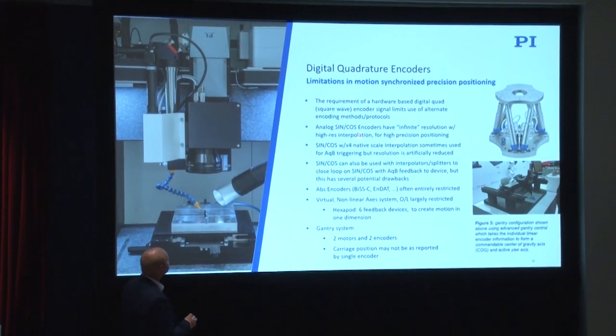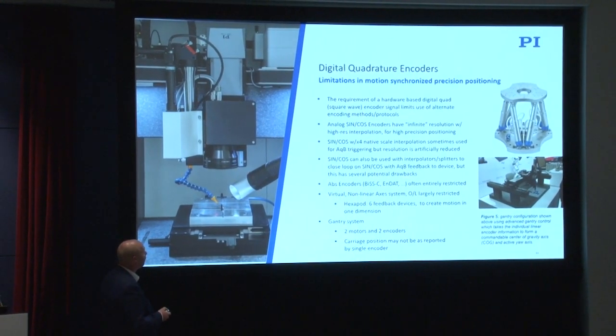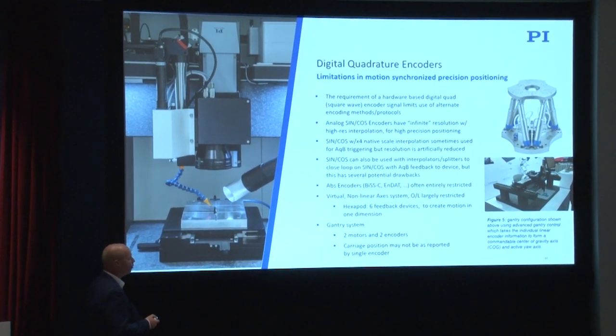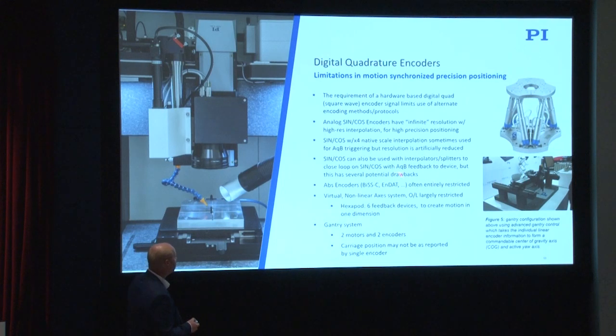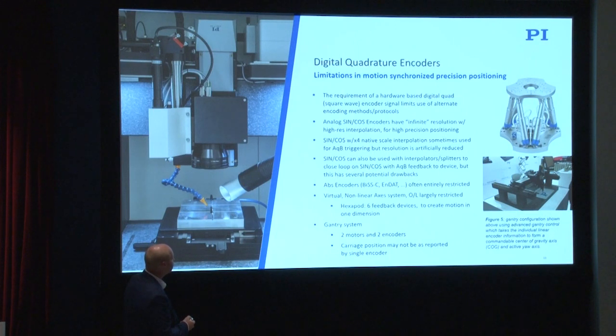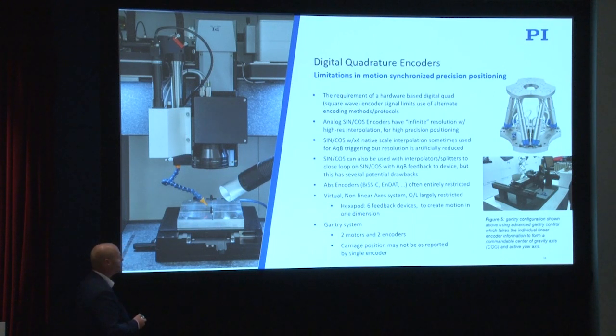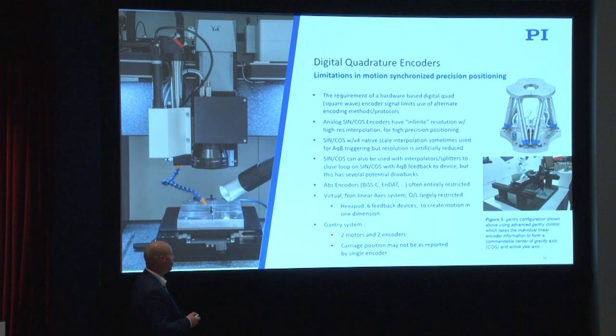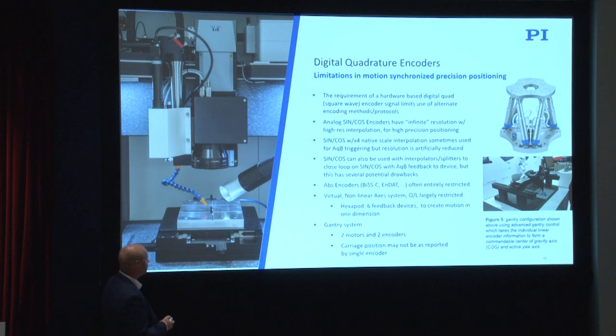This requirement for a hardware-based digital quad really starts to limit the use of other encoding methods and protocols — absolute and sine cosine. Analog encoders have very high resolution, but we restrict that ability by being limited to the pitch of the encoder with quadrature. Using interpolators and splitters to handle sine cosine becomes messy, and in many cases you can't even use absolute encoders — they're just totally restricted — even though they offer safety and other advantages.